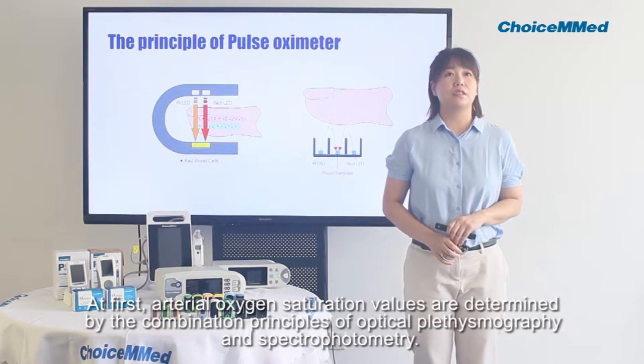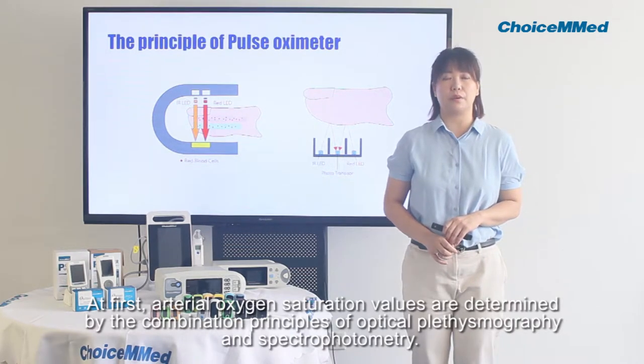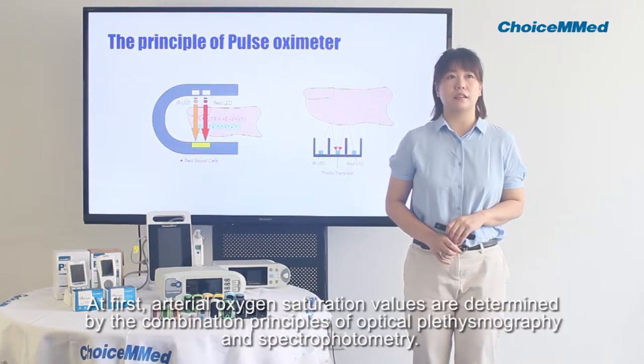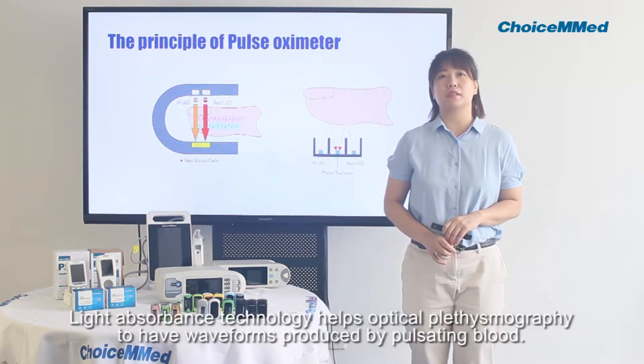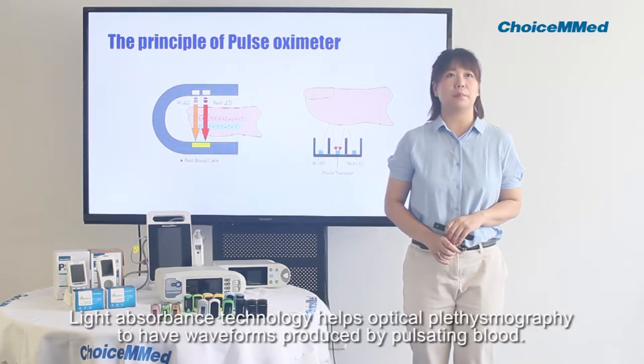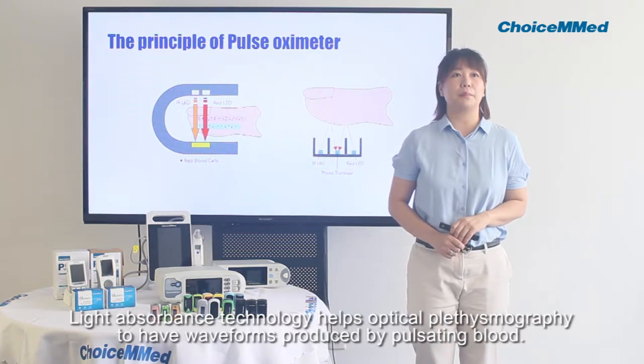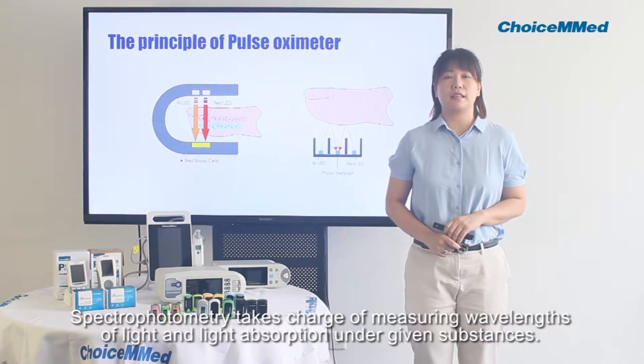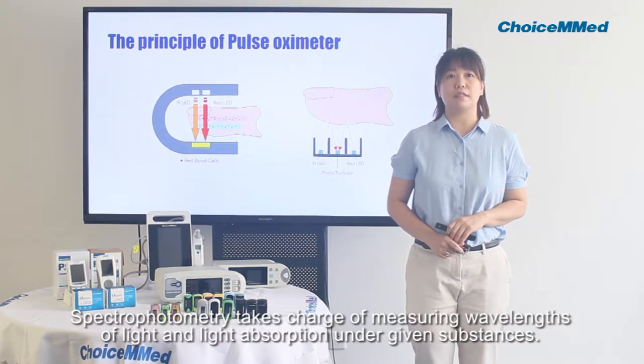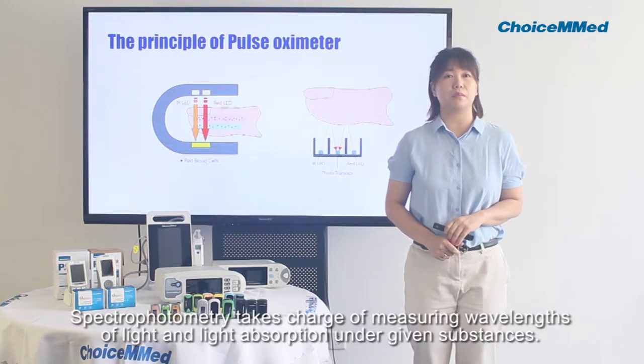At first, arterial oxygen saturation values are determined by the combination of optical plethysmography and spectrophotometry. Light absorbance technology helps optical plethysmography produce waveforms from pulsating blood. Spectrophotometry takes charge of measuring wavelengths of light and light absorption.